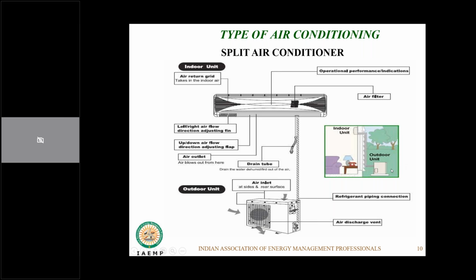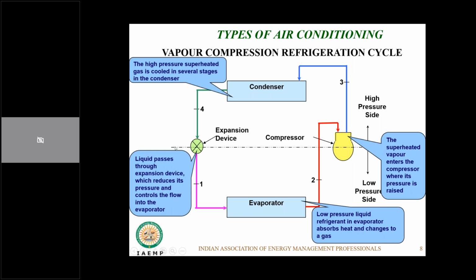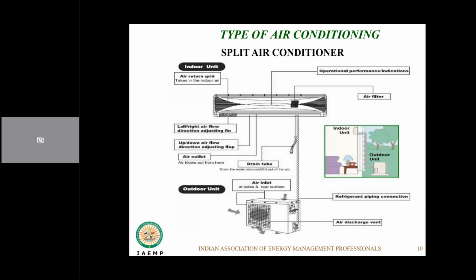So now the evaporator section, basically the line drawn here is what separates your condenser section and your evaporator section. I would rather say it should be crossed diagonally like this, because the compressor normally goes with the condenser and the expansion valve is towards the evaporator side. So what we have here is the condenser and the compressor, which is outside. The good part of this system was that the noise of the compressor and the condenser fan are remotely located, so this became much more silent.